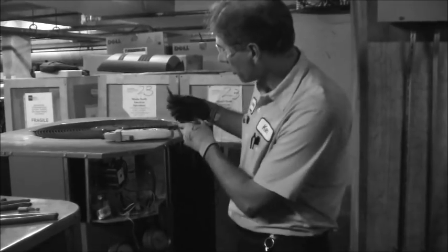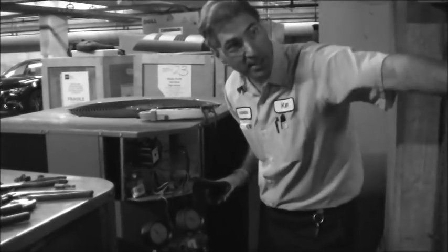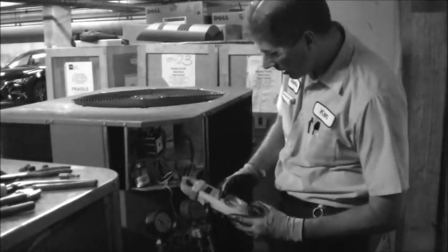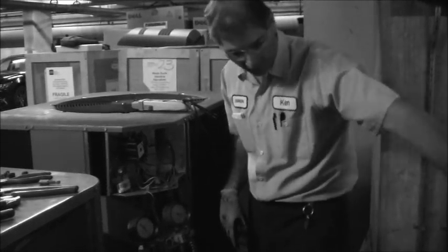Alright, the first thing I'm going to do is just observe my electricity. My disconnect is still in the off position. I'll do an NCV. I got no electricity on either side of my contactor. Normally, you feed a contactor from the top down, but I don't know if that's how they did it. So what I do is I follow the disconnect switch, I follow the conduit, and the conduit is this one right here.